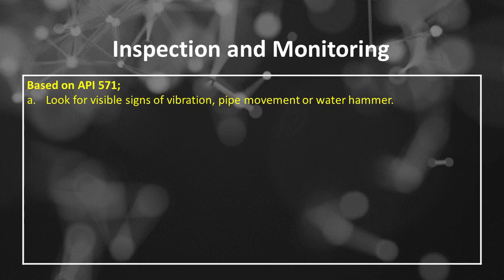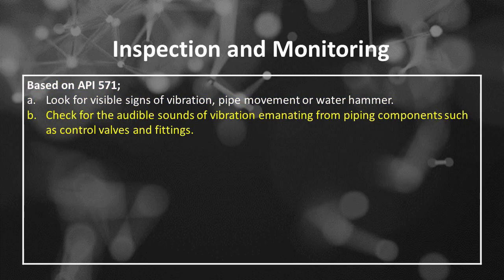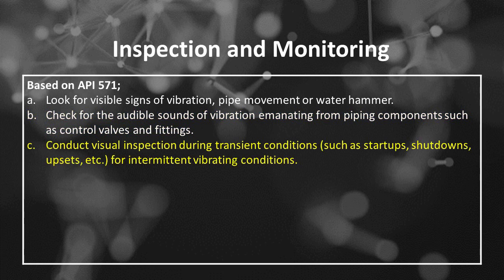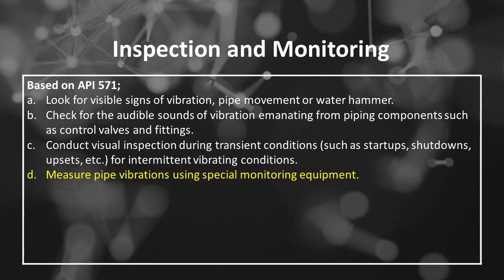Vibration-induced fatigue damage mechanisms inspection and monitoring based on API 571. The first is look for visible signs of vibration, pipe movement or water hammer. The second is check for the audible sounds of vibration emanating from piping components such as control valves and fittings. The third is conduct visual inspection during transient conditions, such as startups, shutdowns, upsets, etc., for intermittent vibrating conditions. The fourth is measure pipe vibrations using special monitoring equipment.